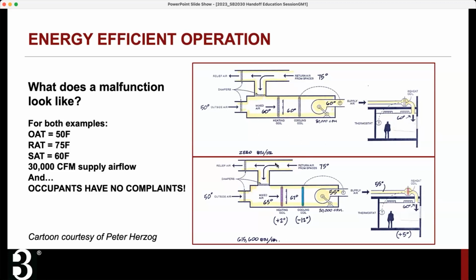Here in the bottom, there are a number of malfunctions. First, the economizer is not functioning correctly. So right off the bat, the mixed air temperature is 5 degrees too warm because they're incorporating too much return air. In addition, there's a heating valve that's stuck open a little bit. So we're adding 2 degrees of heat to the airflow off the heating coil. So now it's 67 degrees. Then the cooling coil is overcooling, dropping the temperature down to 55 degrees, but that's okay. We can still be comfortable because there's a reheat coil here in the VAV box such that the air leaving the diffuser is the same 60 degrees that it's supposed to be.